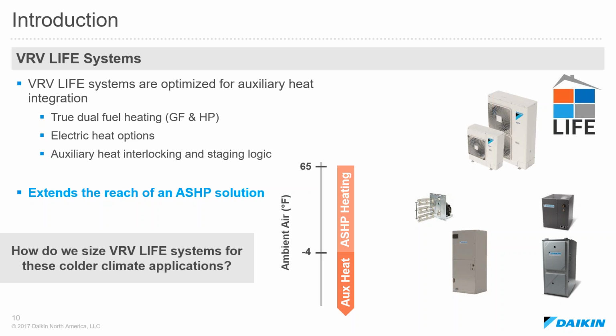There's also some additional ability to integrate electric heat. Some of the indoor units available to the systems have factory options for that, and we also have some control options as far as staging some third-party electric coils on some of the other indoor units. So that's ultimately going to allow us to extend the reach of an air source heat pump solution into some of those colder climates in North America. That's how we're going to be able to have a VRV Life solution in a climate that has a -4 degree or below design day temperature.